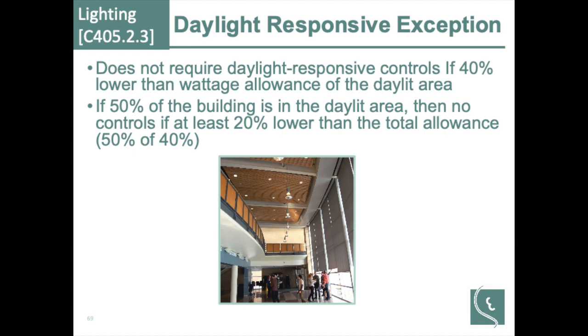Because it's 40% of the weighted area of the building, this is definitely one of those exceptions where, if you can fall under it, it makes your life a lot easier. You don't have to buy the controls, install the controls, or commission the controls.